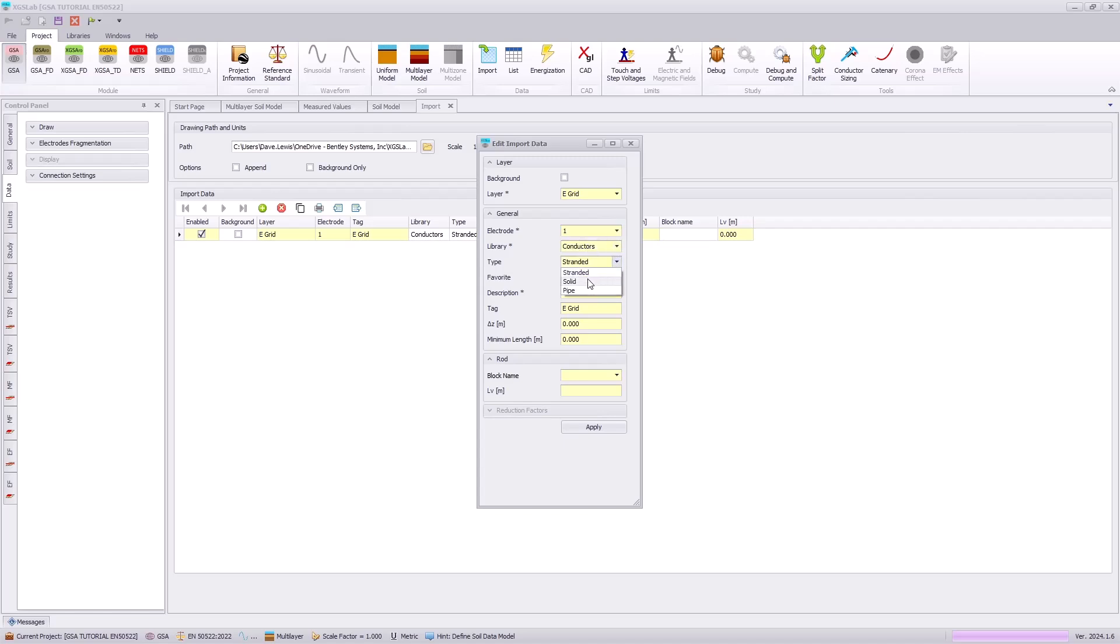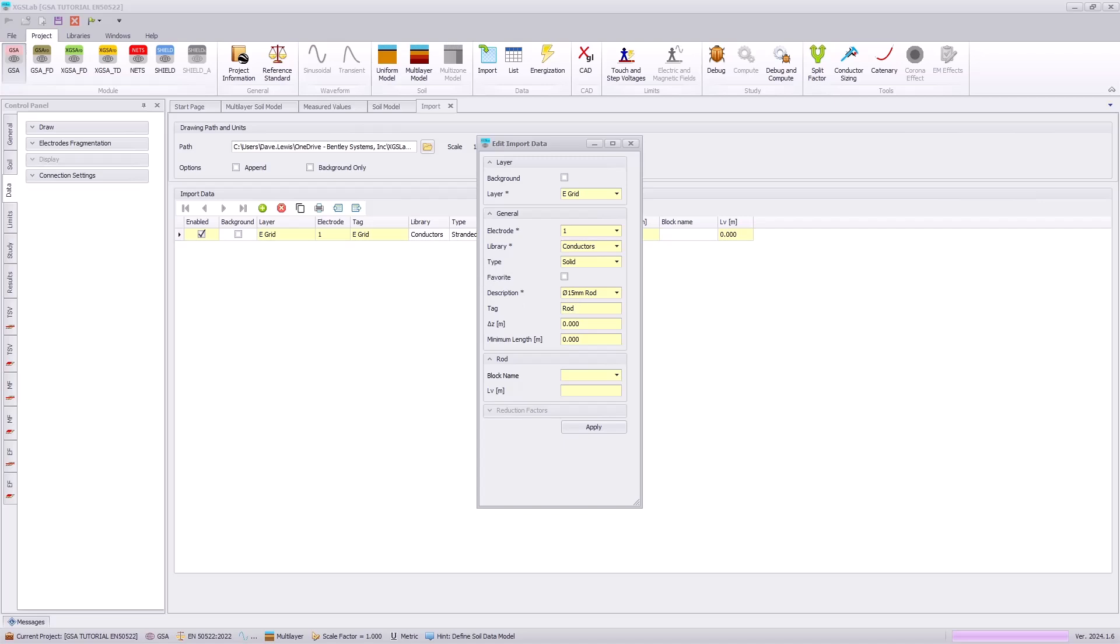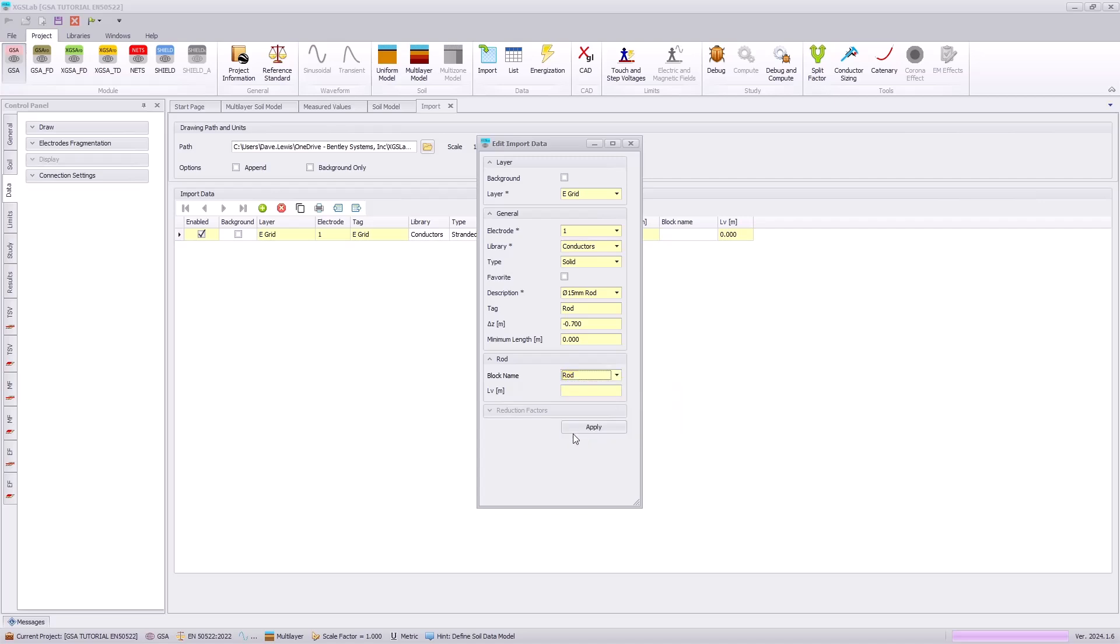And then this time we will use a solid conductor type and navigate to the 15 millimeter rod. Using the tag name rod to give a little better description of that, we will also need to shift this 0.7 meters into the earth. And using this block name drop down, we can specify the name of the block or the cell, as well as the length of our ground rods, which will be 3 meters in this instance.